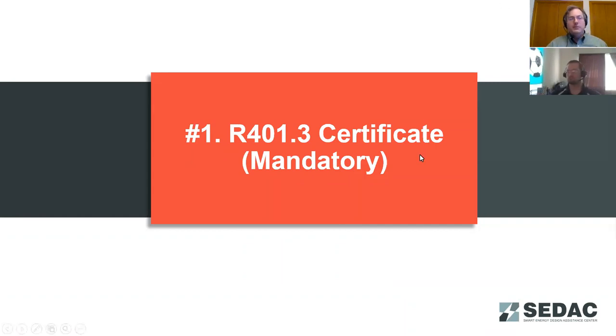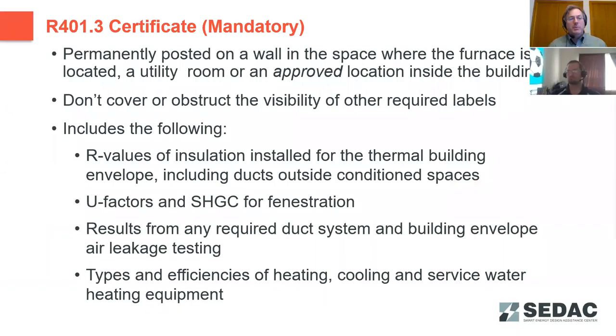So starting in with the certificate, the code calls for a permanently posted certificate that covers several features of the home, and it calls out several things that need to be in it. The location of this typically is going to be found either where the furnace is or in a utility room or approved location. So the 2 places that we normally find this is near the furnace or near the electrical panel. So those are the 2 places we typically find this posted. Obviously, we do not want to cover or obstruct other required labels. So such as on the electrical panel, if we placed it inside the door, we would not want to cover the schedule of the circuits inside. So here it does call out several things and features that need to be on it.